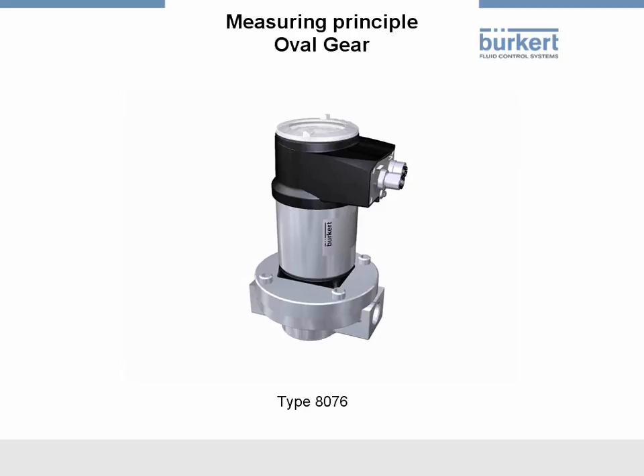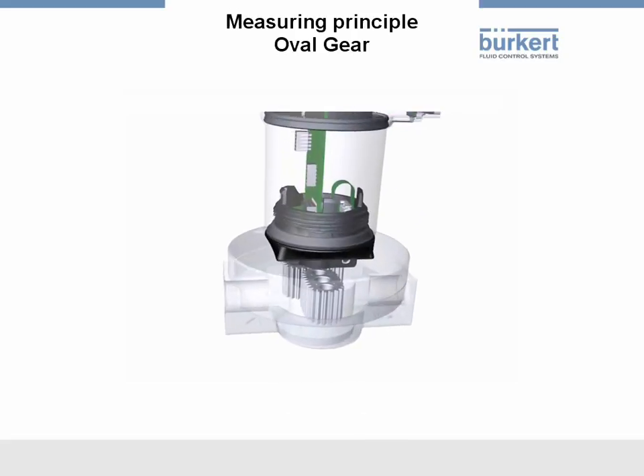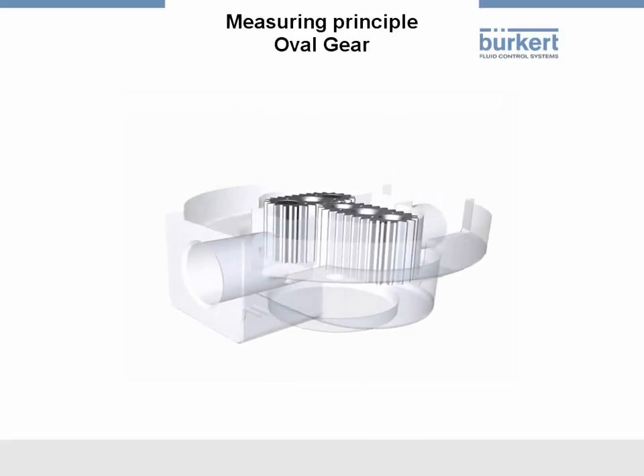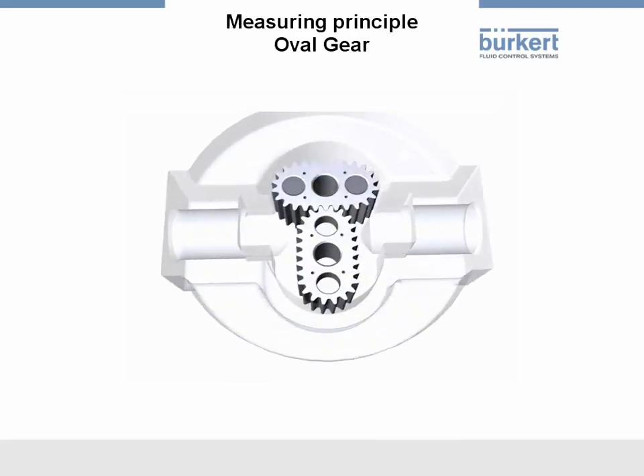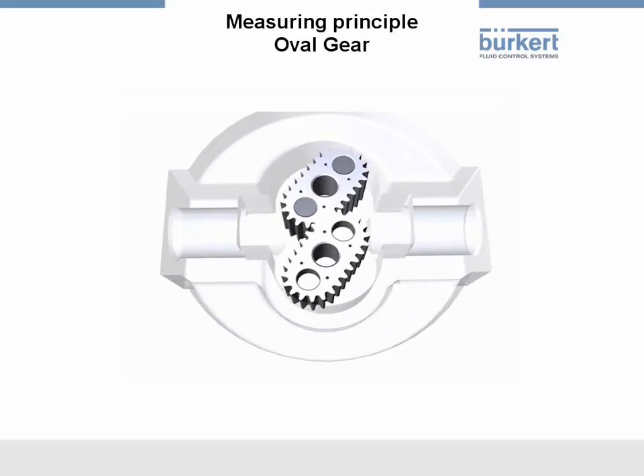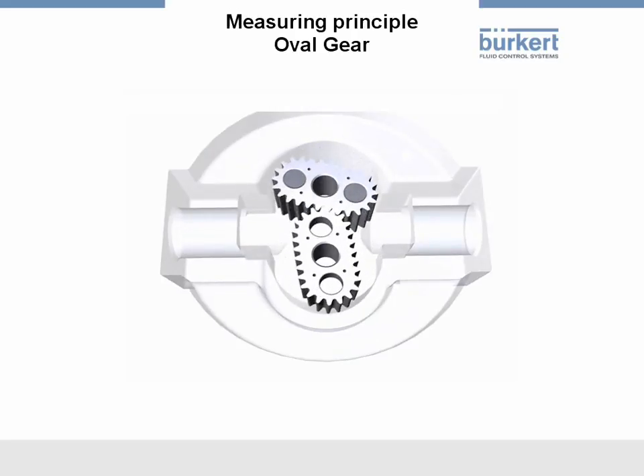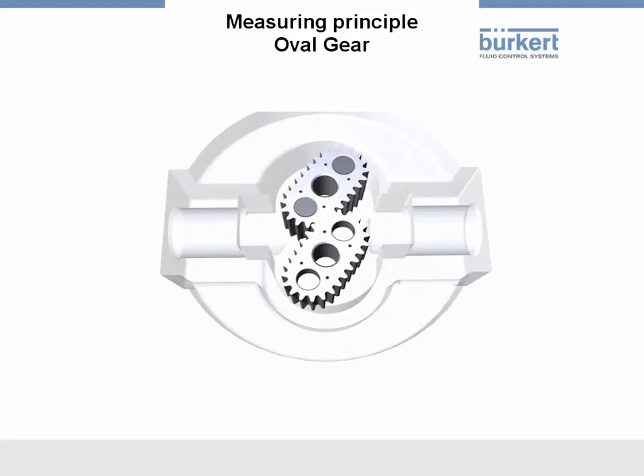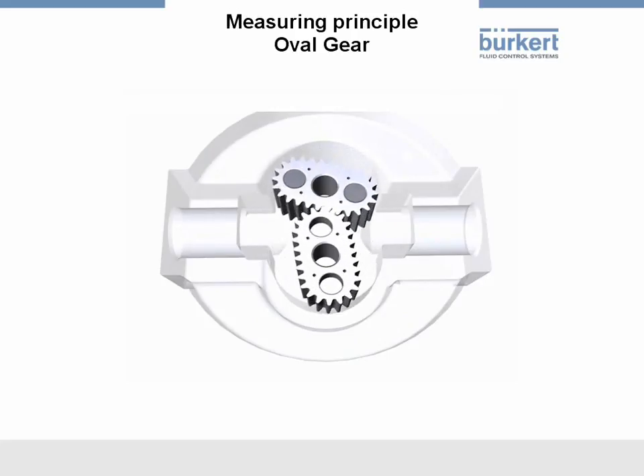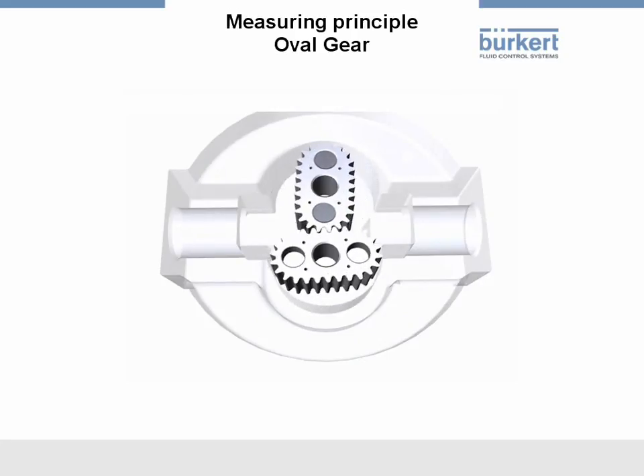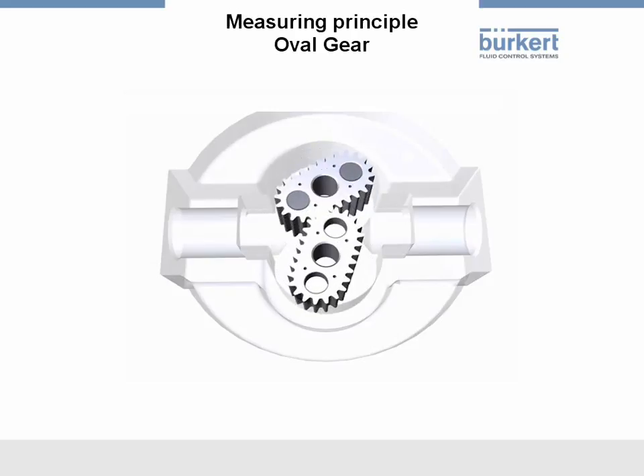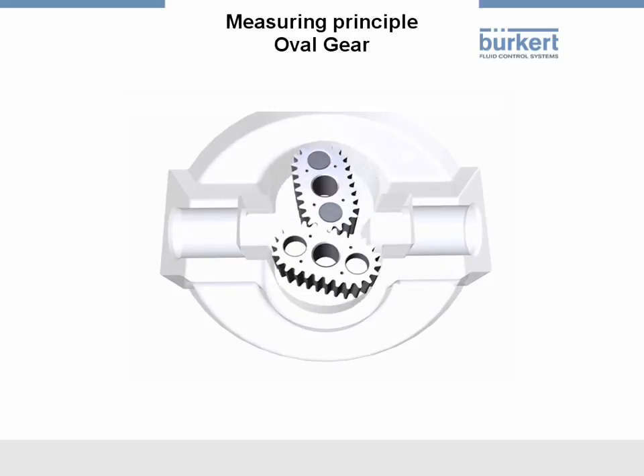But how does a flow meter with oval gears work? As already mentioned, there are two meshing oval gears in the fitting, which are set into motion by a flowing medium. Each oval gear conveys a medium from the inlet to the outlet, forming a closed chamber. For each rotation of the rotor, four times the chamber volume is conveyed between the oval gears and the body.